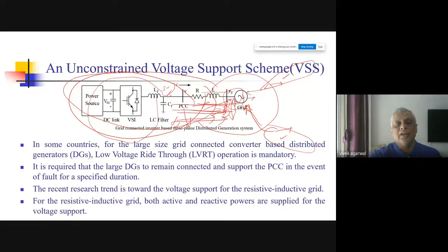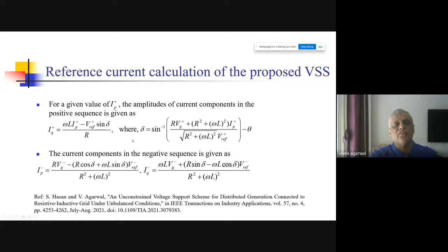What we have done here is a detailed reference current calculation: how much reactive power we should inject into the system during the LVRT is computed here analytically, and then it can be given to the controller, which will use it to adjust its reactive power injection into the system.